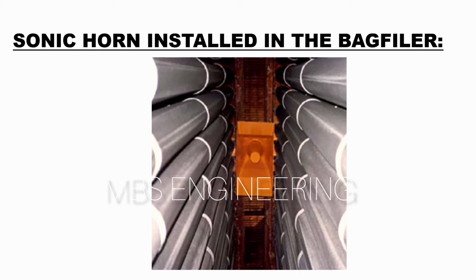Please refer to the picture. A sonic horn is installed in the bag filter. In the bag filter, it is used to prevent blinding of the filter bag. Reduce the pressure drop across the bag filter. Improve the discharge of material and extend the service life of the filter bag. In a bag filter hopper, it is used to prevent dust buildup, eliminate bridging, and sidewall dust buildup, and prevent hopper blocking.